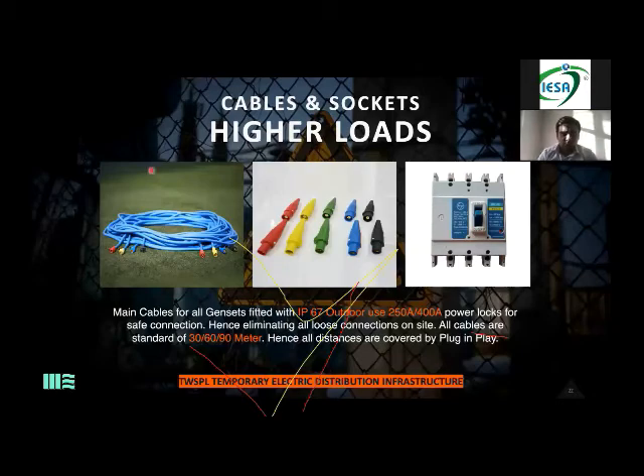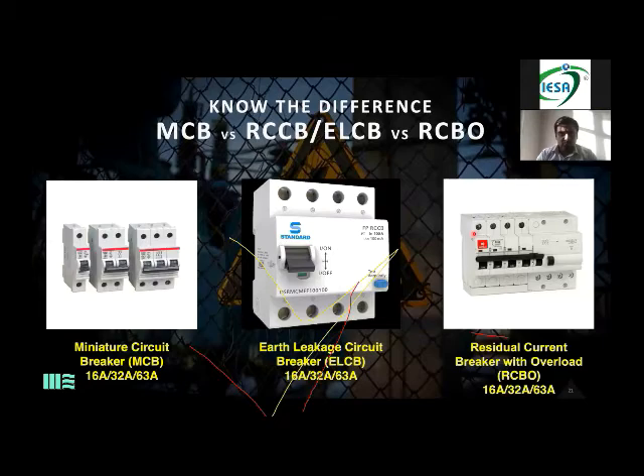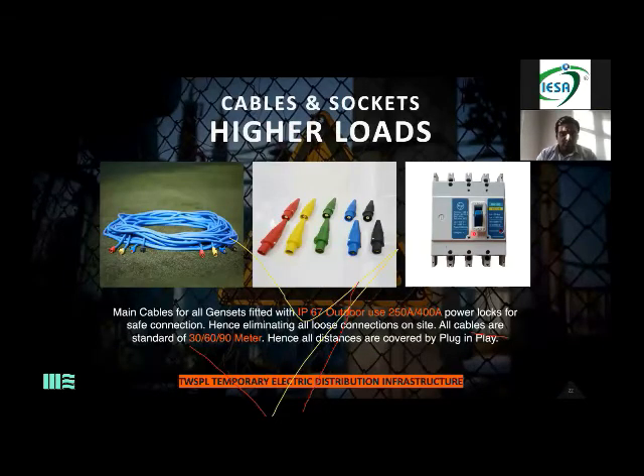So again, the higher the load, the higher the rating. MCBs, I told you, are meant for smaller loads. Now comes the MCCBs. These are meant for the bigger loads. They start from around 100 amps and go up to 800 amps also.